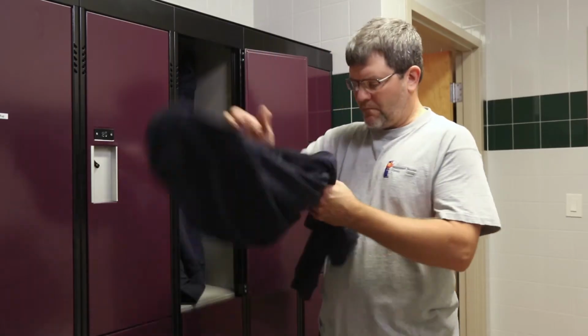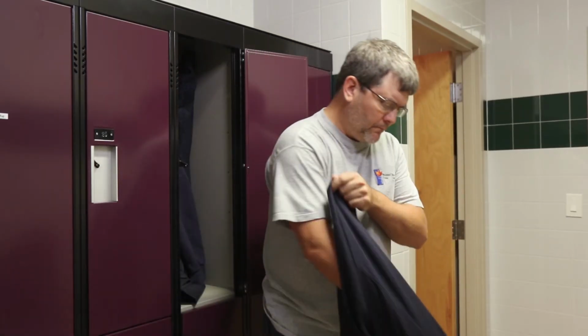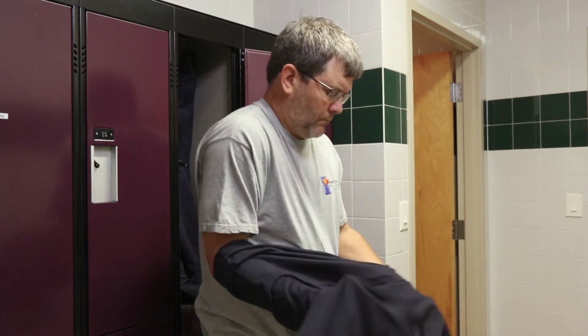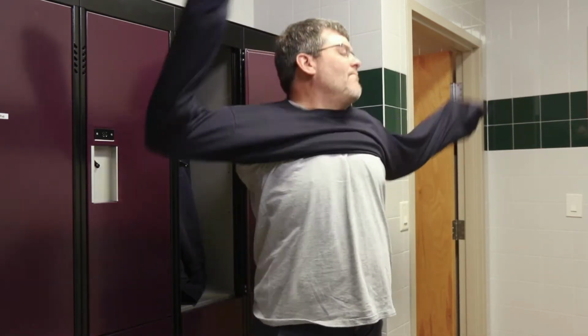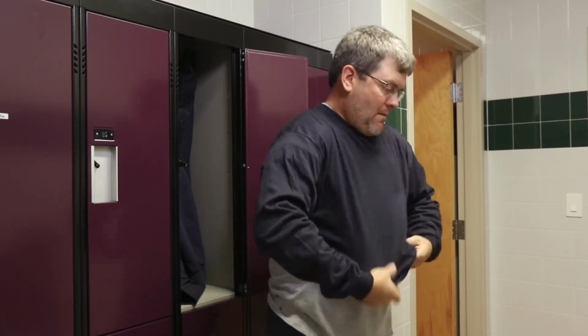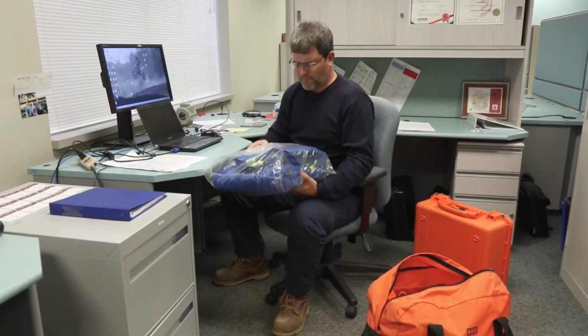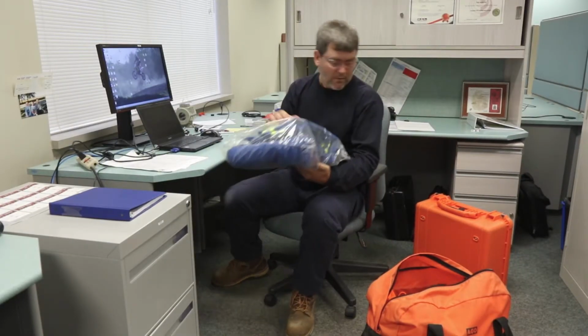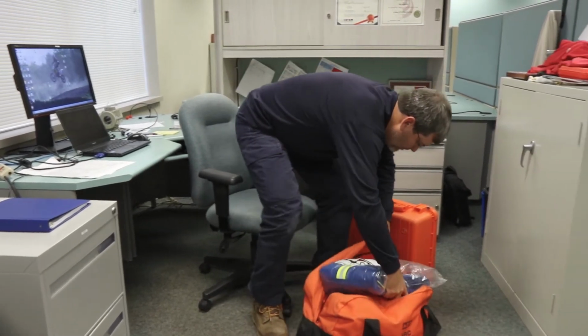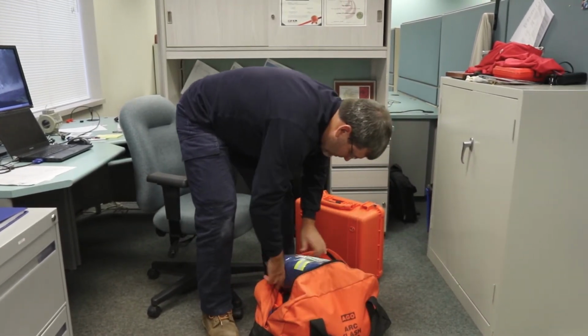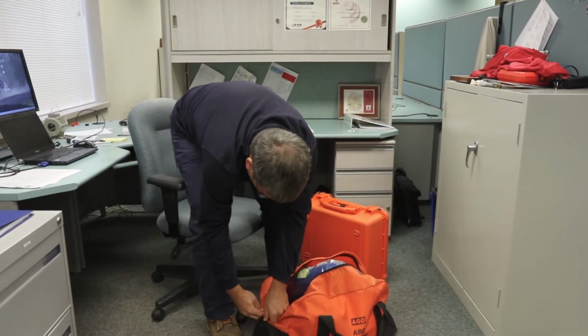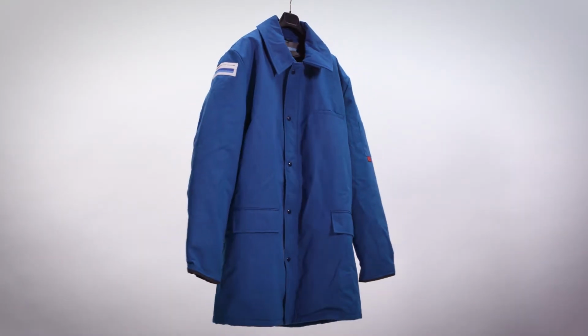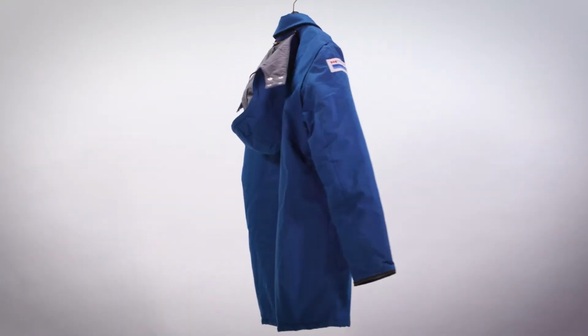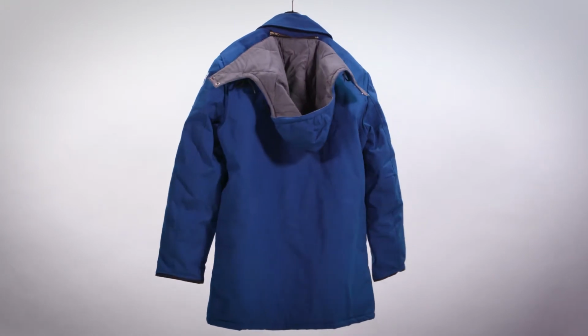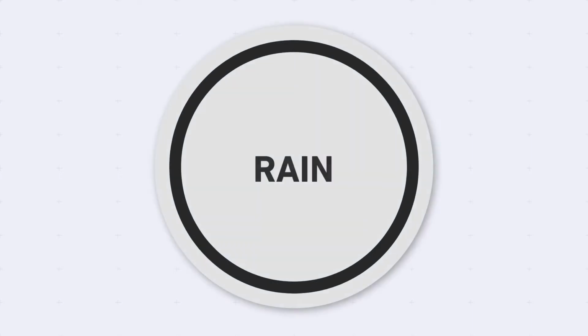Clothing made of natural fibers like cotton, silk, or wool must be worn underneath the outer arc flash protective clothing to minimize skin burn damage if an arc flash occurs. Nomex or equivalent coveralls will be provided to employees working in potentially flammable environments. The material must be Type 3A. A Nomex or equivalent parka will be provided to all inspectors for use in cold environments. Electrical installations should never be inspected in the rain.